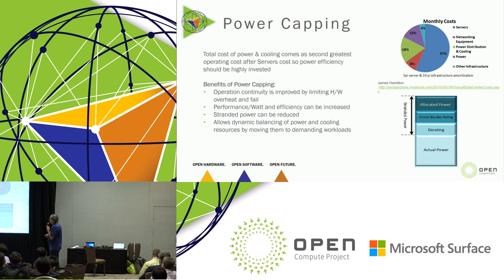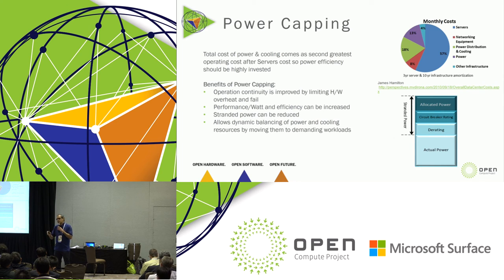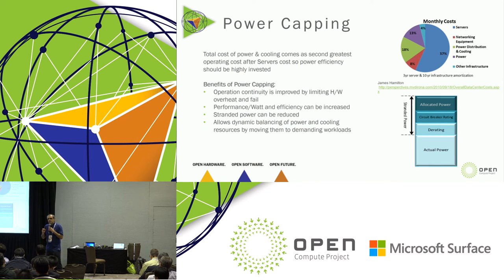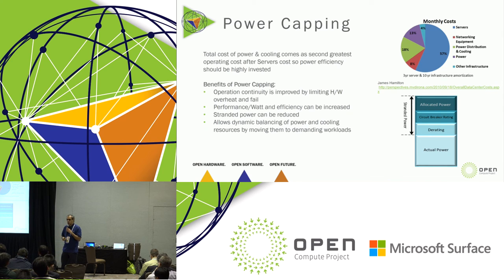Not all workload peaks happen at the same time. Studies show there is workload variation — maybe one server has peak workload for a short period of time, and that performance peak then moves to the next server. By leveraging power capping, we can dynamically balance cooling and power resources and move or share power where it's most needed. We can monitor which workload is critical or highly in demand, serve those servers, and ensure we get the best performance and power utilization.